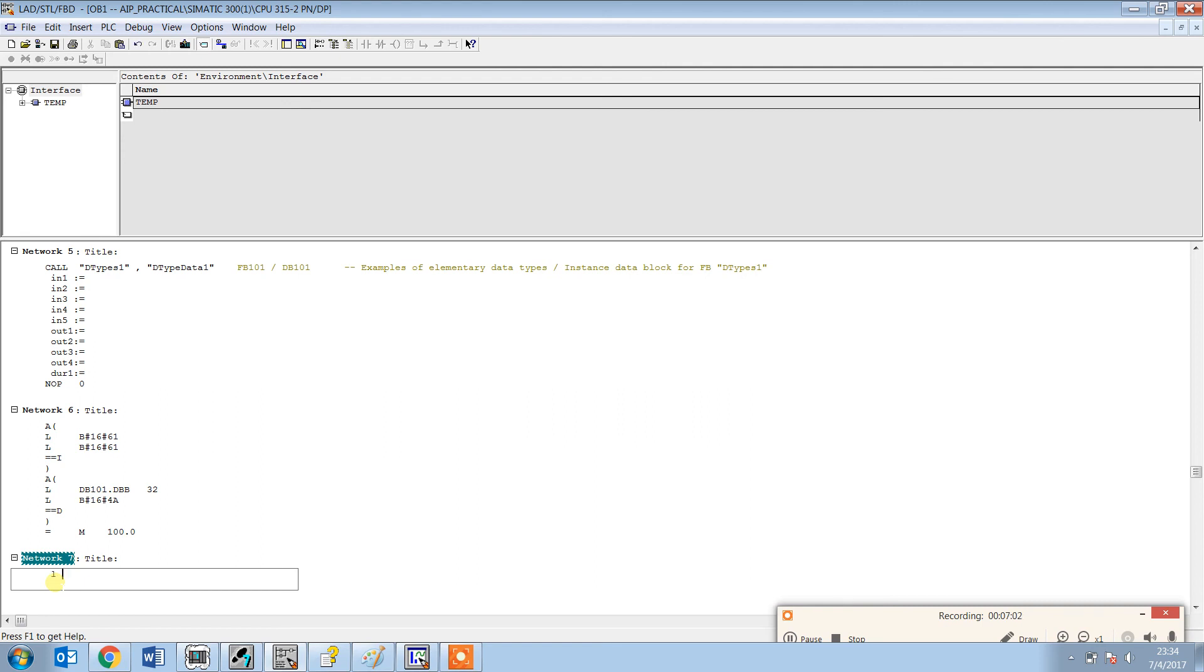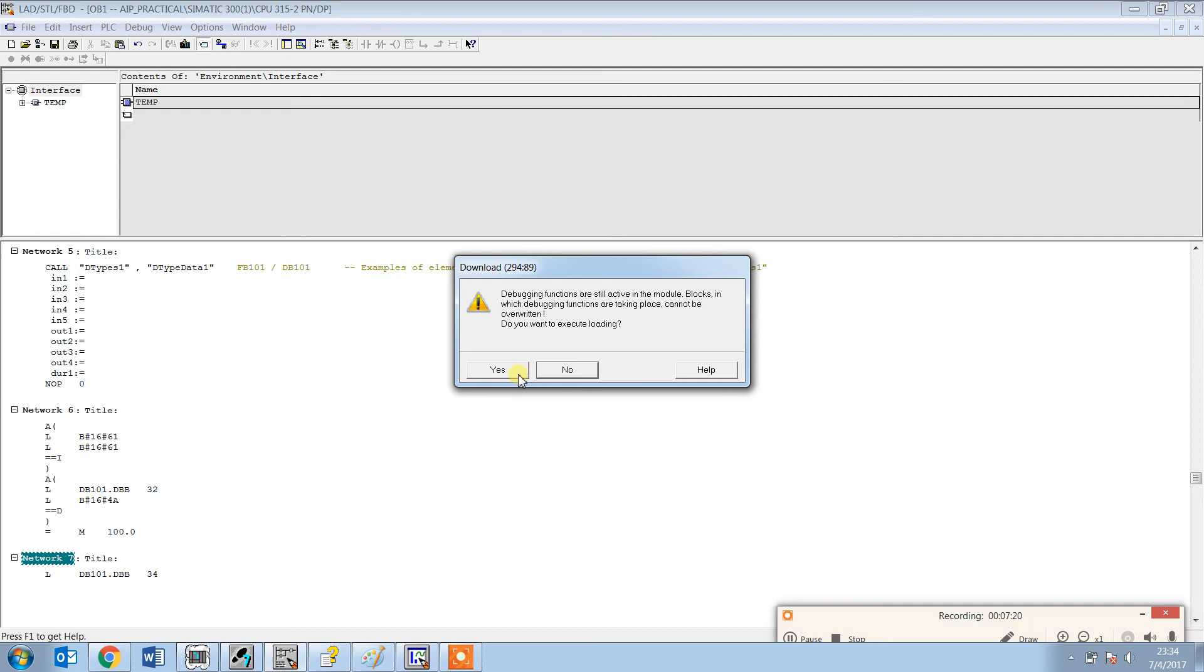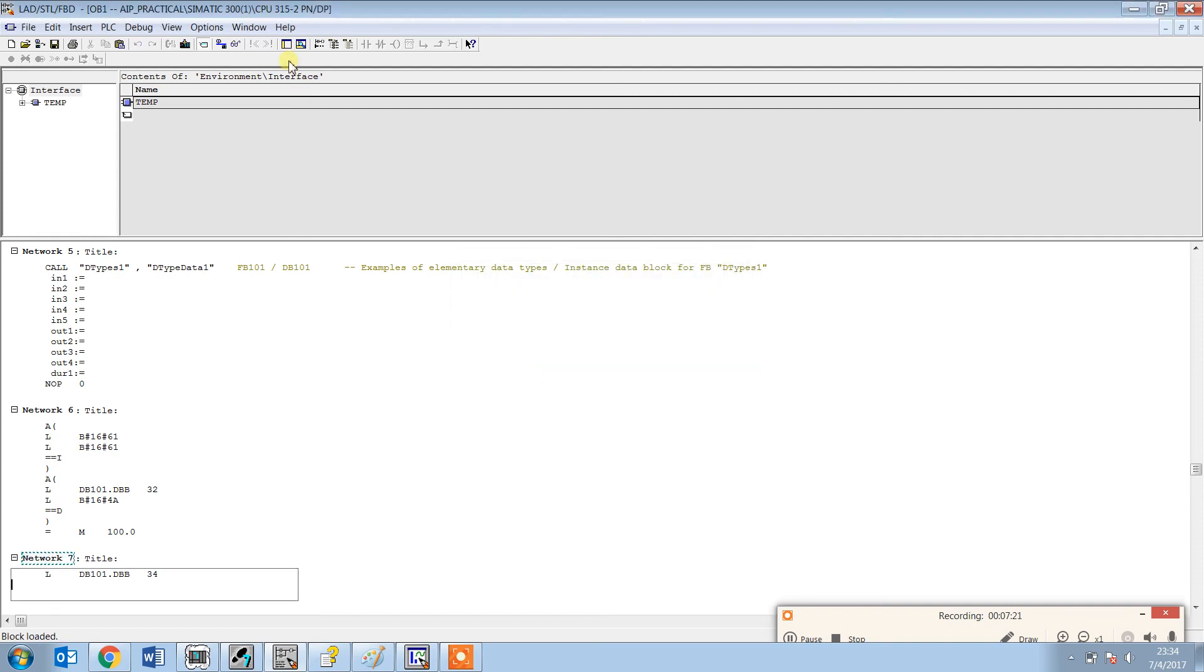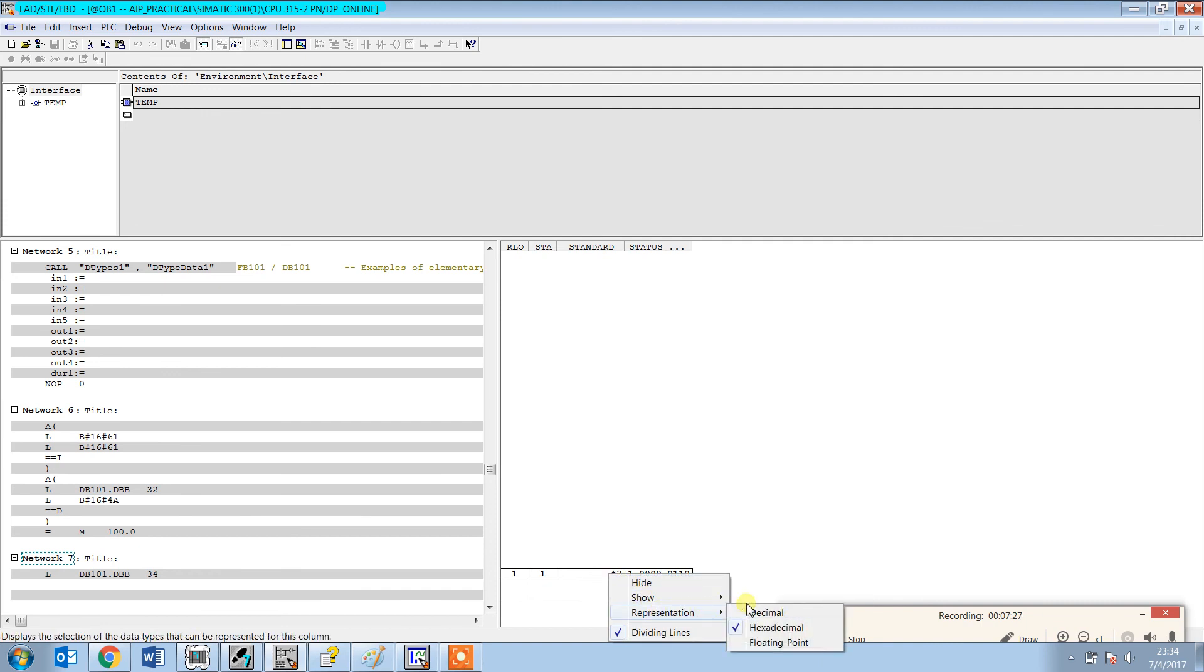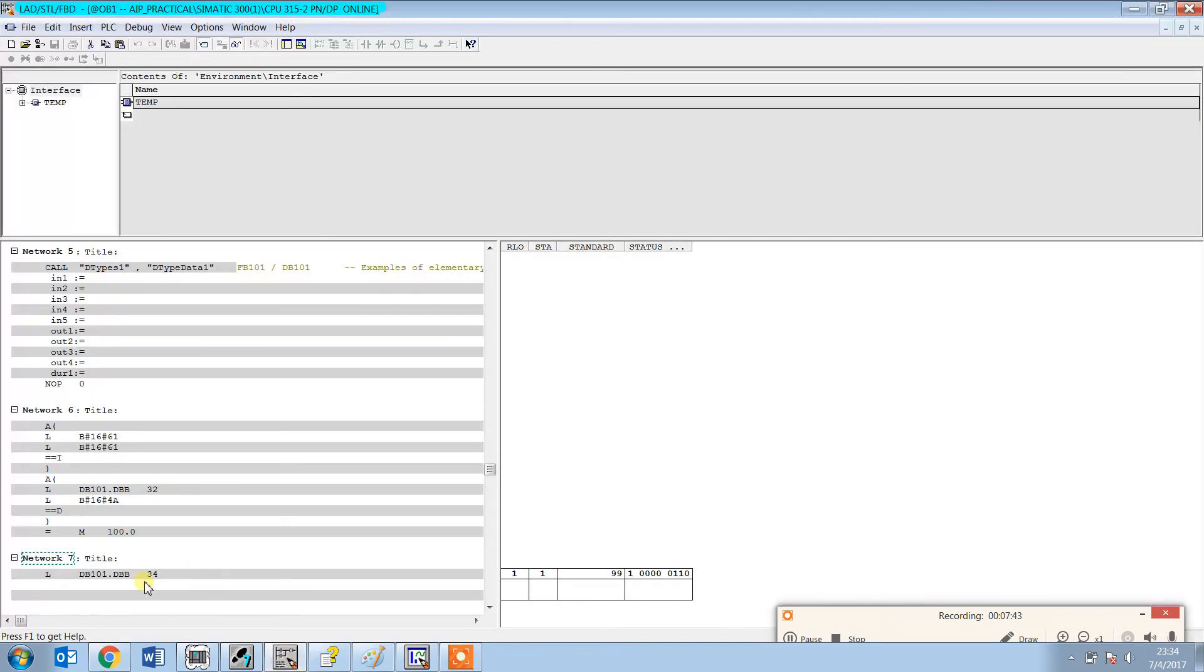Load DB 101.DBB 34 and transfer. Just load it and we can see what value it consists of. You see 63 representation, decimal 99. And 99 we can check here. 99 is 'C', that is the third character out of 'JACK', and we have loaded the DBB 34.